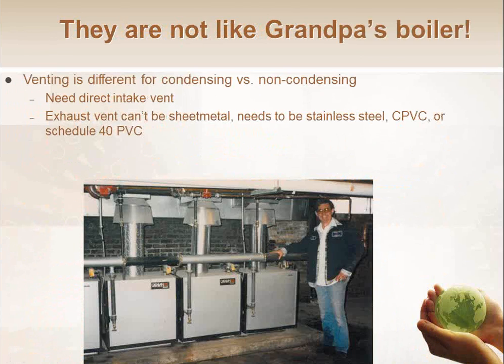The venting is also going to be a different material, right? So the old boilers we use, like the ones in this picture, were vented in sheet metal. That's no longer going to work. Once we get to a condensing state, some of the things that precipitate out of the condensate are going to be acidic in nature, and that will eat up the sheet metal. So you can't vent it in sheet metal anymore when you switch to a condensing boiler. You pretty much have to go to stainless steel or PVC. And obviously PVC is cheaper, so you're going to want to do that whenever possible. So PVC for condensing boilers is going to be the most common venting method.